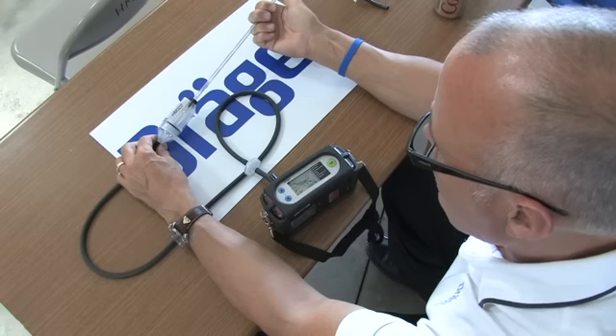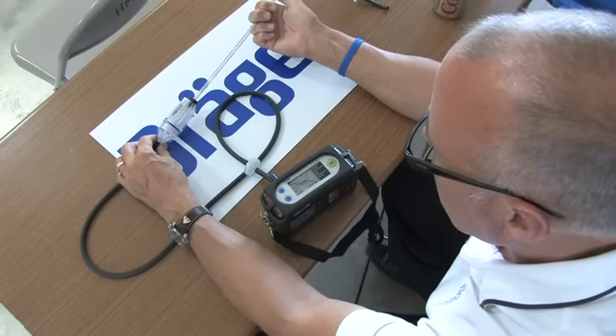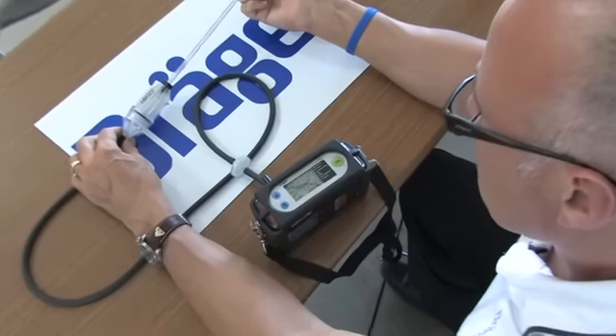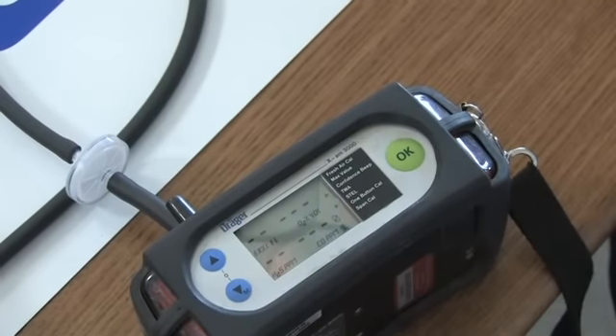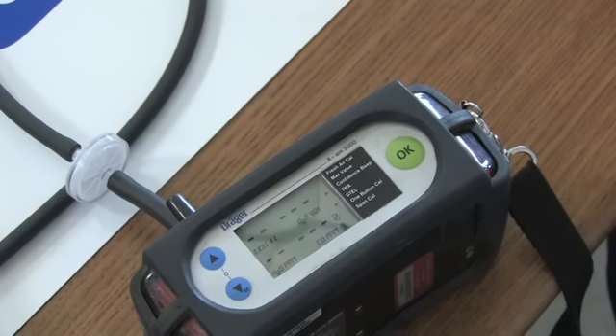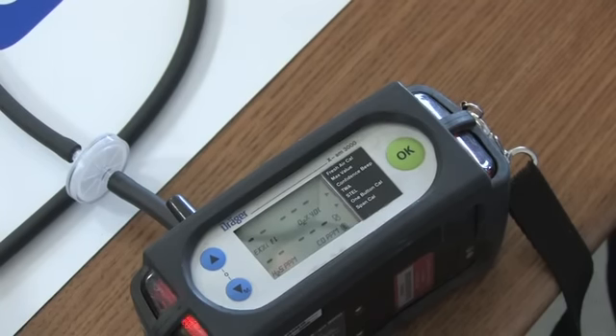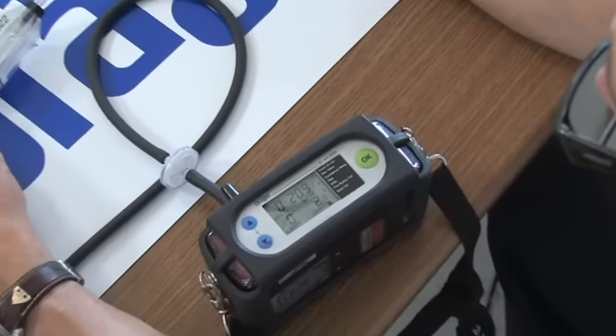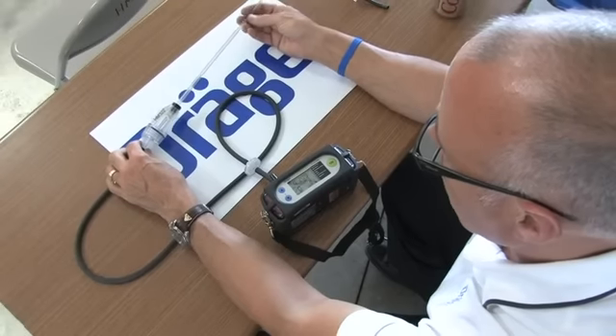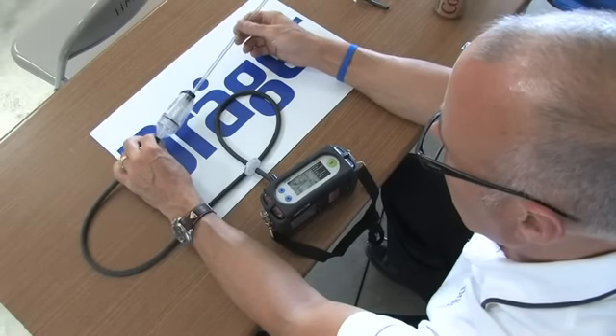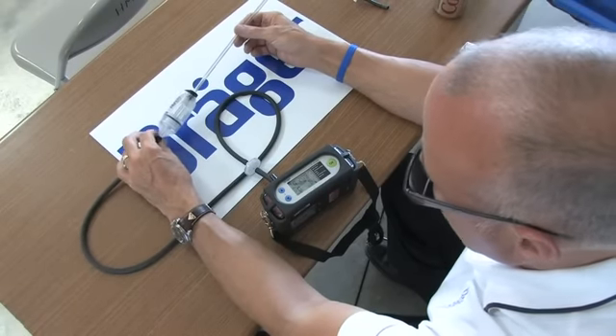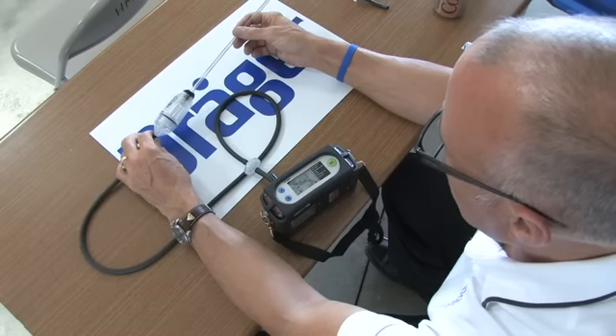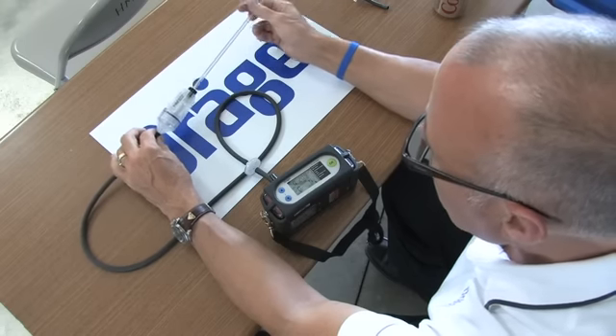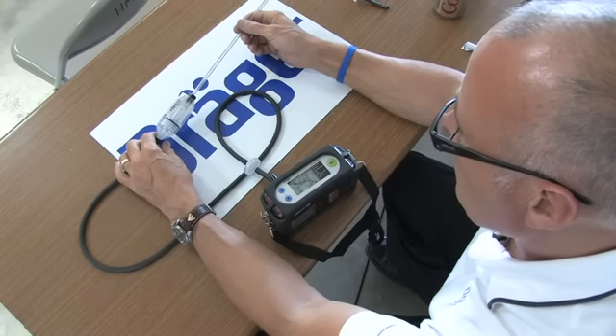There's all the dashes again from a flow fault choke off. And notice the two little arrows now have a line through the middle of them stating that the pump is choked off. The moment I remove my thumb, back to normal operation. And the CO will take a little bit of time to get back down to 0. But I can actually now, after I've done a bump test on the meter, my battery is good. I've checked the pump on the meter. We're back at zeros and 20.9.